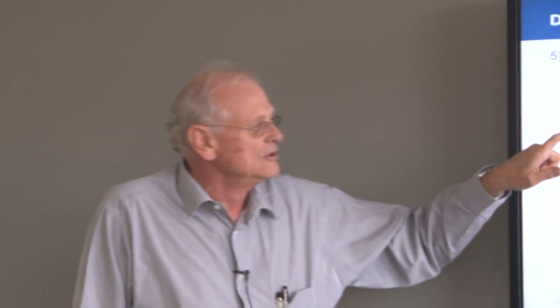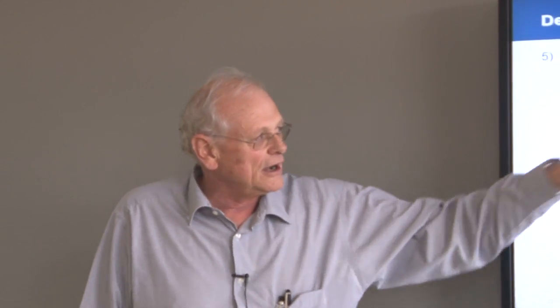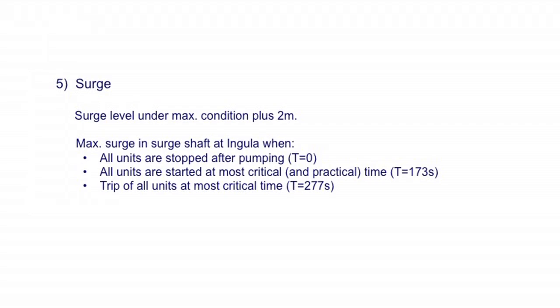We found that for Ingula, if we are pumping and we have to stop pumping, say national control said stop pumping because I need to recover some of the energy. And then he may say 173 seconds after that, because that is the most critical time, start generating again. And I'll show you just now why. Start generation, and then suddenly you get a trip on the total system at time 277. And that's when you get the maximum surge. So it's playing around with all sorts of conditions. And the steel liner has been designed according to the European code, CECT.